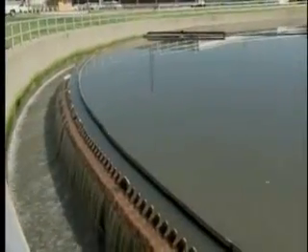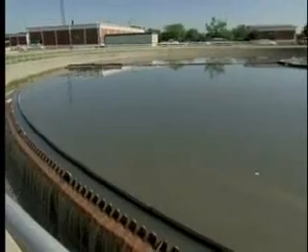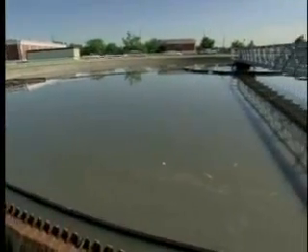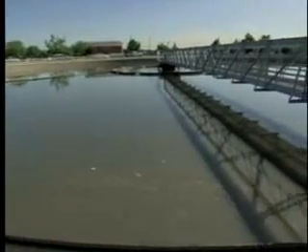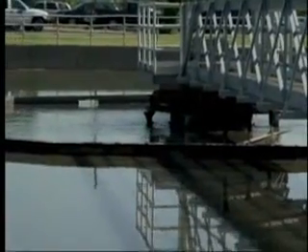And these are called primary clarifiers or primary sedimentation tanks. Screenings was a physical type of treatment. Grit removal was a physical type of treatment. And primary clarification here is also a physical type of treatment. What we do is we slow the wastewater down enough to where settleable materials will settle and readily floatable materials will float. We slow the speed of the wastewater down to about 1 foot per minute in this process.